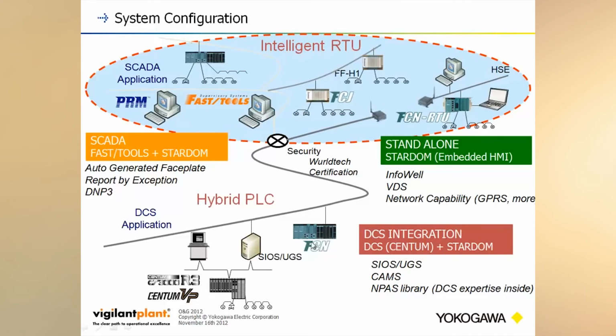Here we can see how we integrate into a DCS. We can either integrate through Modbus, whether serial or Ethernet. If you have a Centum system, we can come in through SIOS, or with a newer Centum system, through the Universal Gateway, which makes it very easy to come straight into Centum. Also, if you have an ALR or ALE card, you can deploy Modbus on your Centum system and come straight in via the Modbus I/O system.